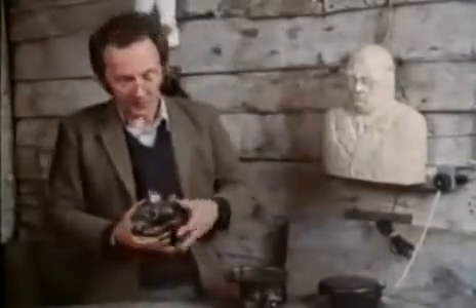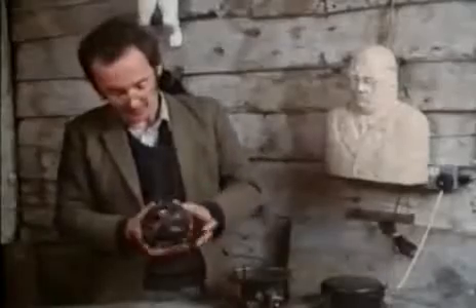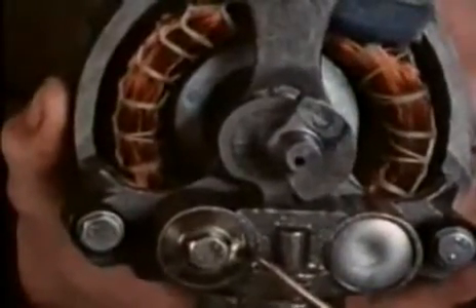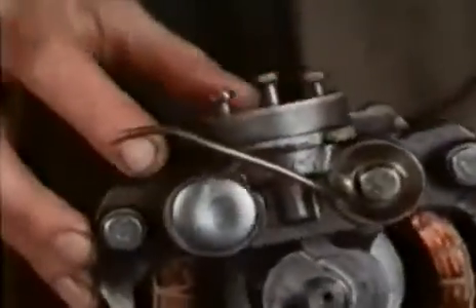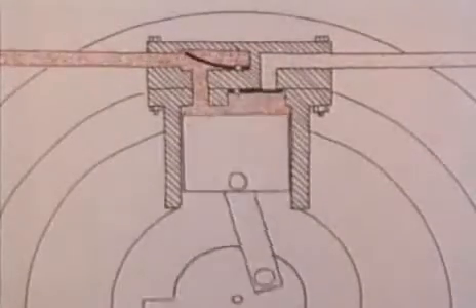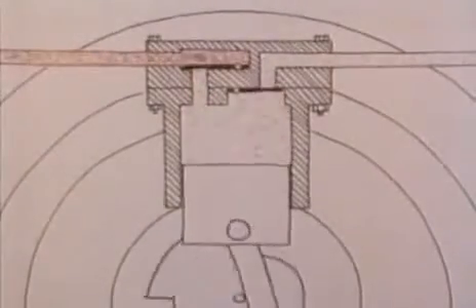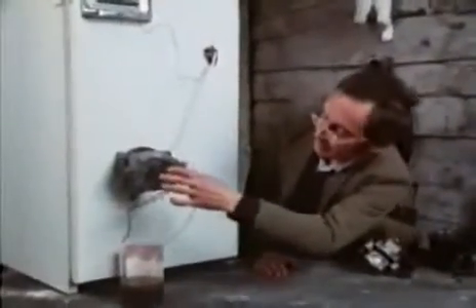The compressor itself is really a little tiny lump that fits on the end. If I turn the motor around, I think you can see the piston going up and down. It's all very solidly made, because in the life of a fridge, it goes round several thousand million times. Inside, there are 2 reed valves, which let the refrigerant in one side and out the other. On this model, if we start the compressor going, you can see the piston flies up and down at a fair rate, and the refrigerant comes in one side and is pushed out the other side.